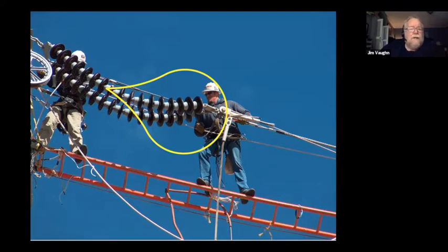But if I stick a conductive object like a lineman inside of that uniform collapse, I disturb that field and I create a movement or a swelling of the field that can push the voltage up the insulators at a higher rate. So if I position my bucket and myself next to a string and I get above that conductor closer to the structure, the bucket and the men in the bucket can create a change in the field, and it can change the voltage collapse over the length of the insulator, which can create a flashover.